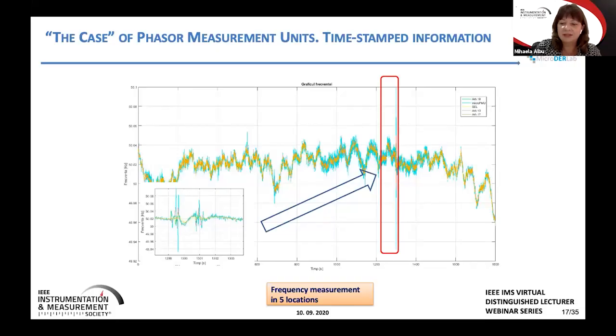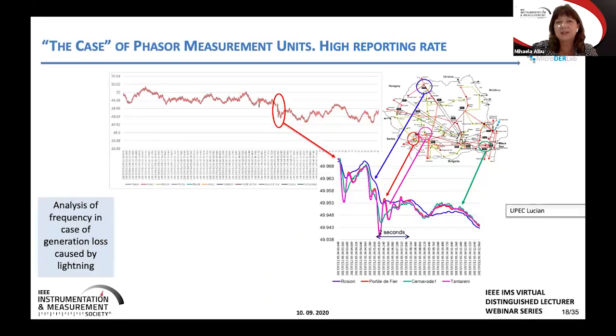This is possible to analyze only if we have this timestamp. Again, it's not necessary to be online with fast communication. It's post-processing analysis. Also, we benefit a lot from the high reporting rate, although, as seen, ideally we would need point-on-wave, and there are a lot of initiatives to embed into the PMUs also measurement results including point-on-wave. Actually, in the micro PMUs, this is already done for finite time intervals.